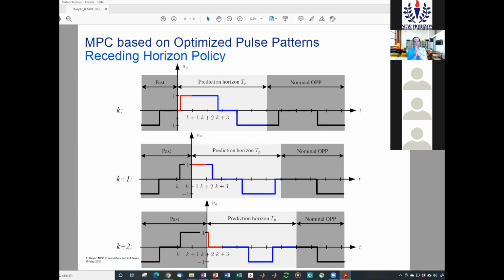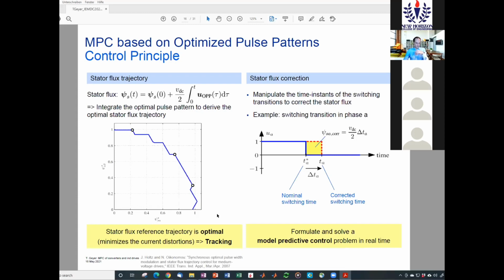So the switching frequency, then you load the optimized pulse pattern. You have offline integrated up the stator flux trajectory, computed this trajectory for each pulse pattern. The magnitude is 1, unless you do field weakening. The position you get where you would like your stator flux to be comes from the rotor flux and the torque. Now you need to control your stator flux to that reference point, and you do this by changing the time when you switch a little bit.